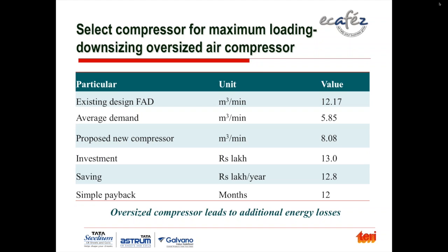The existing FAD, as you can see, in the plant was 12.17 meter cube per minute. Sorry, that is the design volumetric capacity of the compressor. The demand in the plant was 5.85 meter cube per minute. We suggested the unit replace the air compressor with a smaller one of 8 meter cube per minute. Why 8 meter cube? Because at certain times the peak air consumption was going up to 7 meter cube per minute. So there was a peak demand at certain points, although the average was about 5.85.